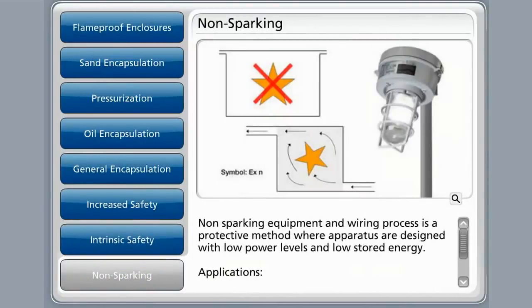Non-sparking equipment is a protective method where apparatuses are designed with low power levels and low stored energy. This ensures that any arc produced during normal functionality or as a result of equipment failure has insufficient energy to ignite the hazardous atmosphere. The general application for non-sparking protective methods would be used for motors, lighting, junction boxes, and electrical equipment.